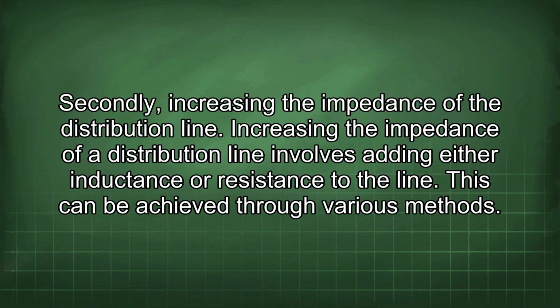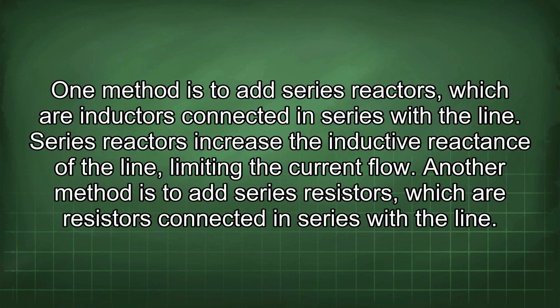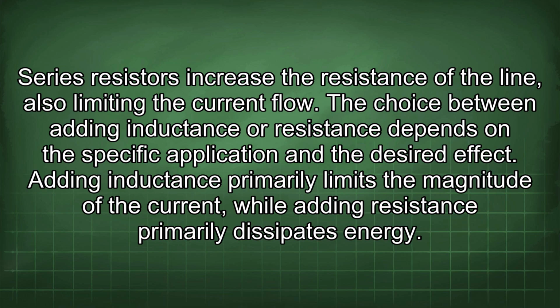Secondly, increasing the impedance of the distribution line. Increasing the impedance of a distribution line involves adding either inductance or resistance to the line. This can be achieved through various methods. One method is to add series reactors, which are inductors connected in series with the line. Series reactors increase the inductive reactance of the line, limiting the current flow. Another method is to add series resistors, which are resistors connected in series with the line. Series resistors increase the resistance of the line, also limiting the current flow. The choice between adding inductance or resistance depends on the specific application and the desired effect. Adding inductance primarily limits the magnitude of the current, while adding resistance primarily dissipates energy.